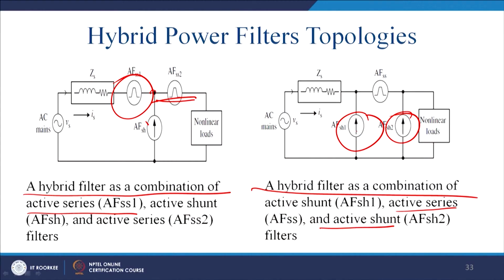We have Professor Bhattacharya's work on it, but this was missing. So, this voltage is maybe an add-on. Your PCC voltage may be less due to the sag, so you do not have a problem, but here your PCC voltage may be high, but your voltage has been clean, and thus you give a total solution, and ultimately you have segregated the problem. Maybe the dominant harmonic will be produced by AFsh1, and AFsh2 may produce the other higher order harmonics, and you get a total optimal compensation.